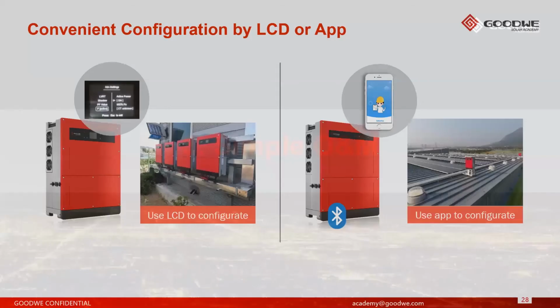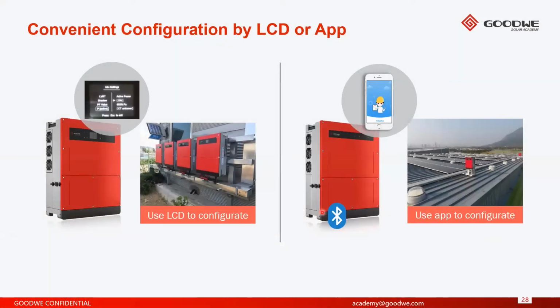In terms of operation and maintenance, we have LCDs on one side. Our MT series inverters, not so much the HT, come with an LCD display, which allows the installer to commission, operate and change the settings from the front of the screen itself. On the right-hand side, we have inverters with a no-LCD option, which simply has a series of LEDs on the front. These inverters need our SolarGo app to be configured, and typically we configure them by Wi-Fi. In the future we'll be introducing a Bluetooth solution, which will allow the SolarGo app to be connected directly to the inverter for commissioning.